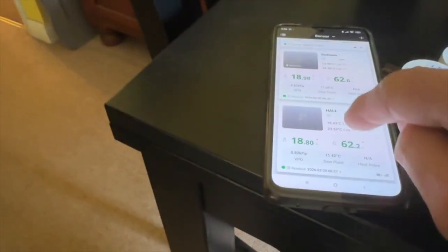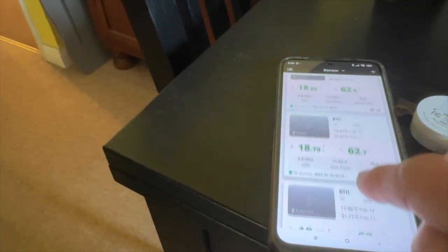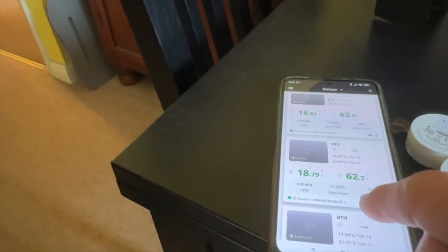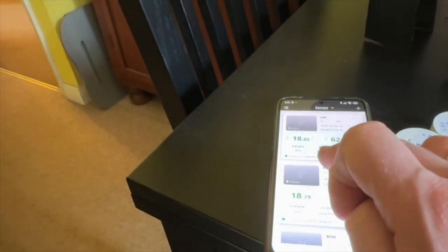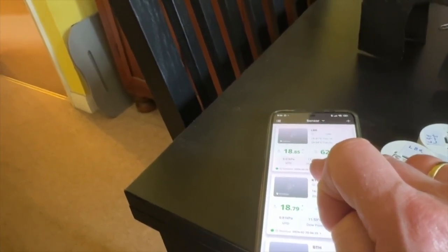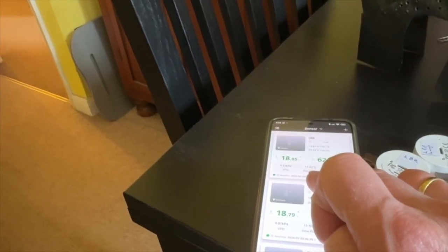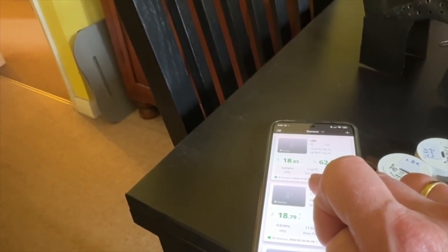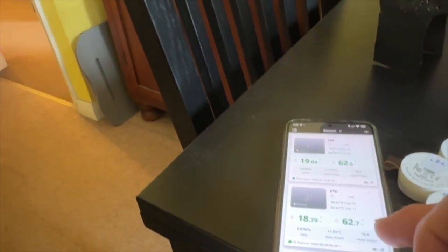These are now calibrated, and you'll see the dew points are more or less aligned with each other now. So the dew point is a measure of the amount of vapour in air. All of the numbers are in line, but do you see the dew point? The dew point is 11.6, and it's really high. I don't know what the outside temperature is, but I think it's probably about 6 or 7. They say it's warming up today, but we've got a front coming through.